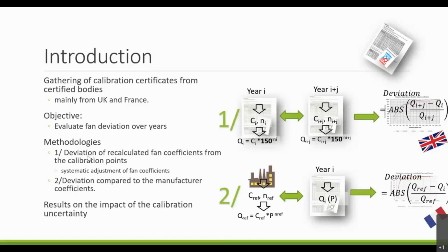In the second part of the study, we have done it the French way. That means with no systematic adjustment of fan coefficients, but keeping the manufacturer coefficients. Well, in France, they keep them as long as they are good enough. So we have compared the flow rate given by the device with the manufacturer coefficients with the flow rates given by the calibration device, and we have plotted the deviation also. At the end of the study, we have also estimated the impact of the calibration uncertainty on the results.